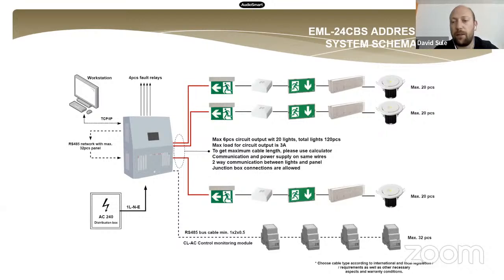The panel has two-way communication with the lights. That means the panel can read any address of the system with the LED current of the light. So we can read for one light how much the current of the LED is and what the last test result was, or we can read all of this information together for all luminaires, because the panel has a special maintenance mode. That means we can set up the panel for 30 minutes of full speed communication with the lights, so every 30 seconds to 1 minute, all of the addresses, all of the test results, and all of the communication signals can be read by the panel.